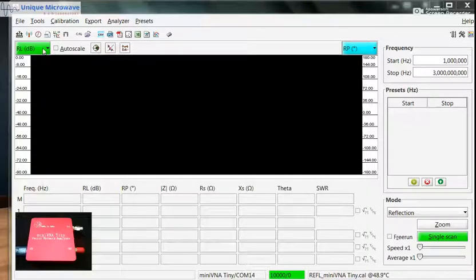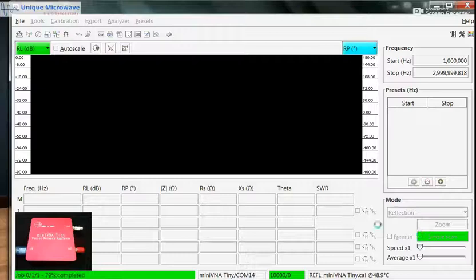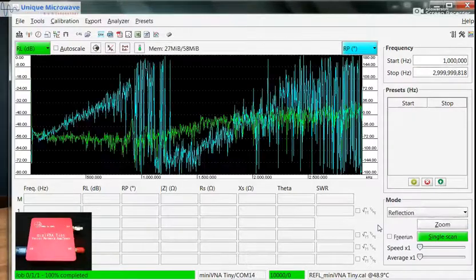This green button indicates the magnitude of reflection coefficient in dB, whereas this blue button indicates the phase of reflection coefficient in degrees. We can now start our measurement by clicking the single scan button. The green line represents the magnitude of reflection coefficient, whereas the blue line represents the phase of the 50 ohm match load. Here are the values in dB, and here are the values in degrees.